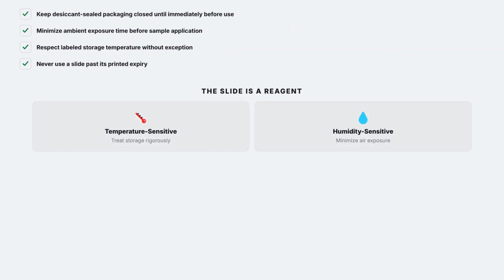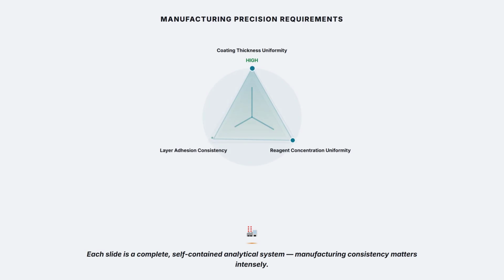Concretely, keep the desiccant sealed pouch or cartridge closed until immediately before use. Minimize the time a slide sits exposed to ambient air and light before sample application. Respect the labeled storage temperature without exception, and never use a slide past its printed expiry regardless of how it looks. Manufacturing consistency across a slide lot matters more here than in wet chemistry, precisely because each slide is a complete, self-contained analytical system rather than one component mixed with fresh reagent at test time. A coating thickness variation of even a few microns in the reagent layer can shift the reaction's kinetics measurably.